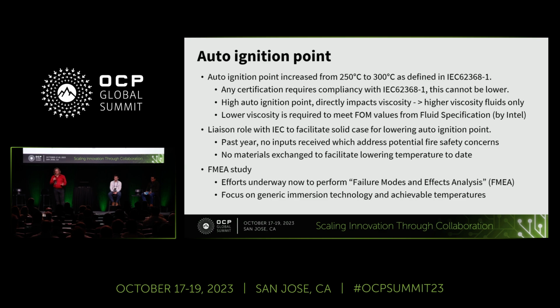A couple of highlights that have changed since revision 2.0: the auto ignition point has been increased from 250 to 300 degrees Celsius. Why? Is it because 250 degrees C is dangerous? Actually no - it's because IEC requires that. So if you want any kind of certification, UL or CE, you must be at 300 degrees Celsius anyway. We're not in a position to recommend anything lower, because it would prevent any kind of recognition.